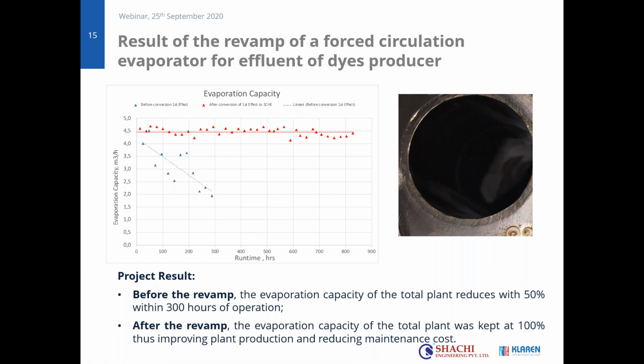So what is of course important then is what was the performance after this revamp, and you can see this in this figure, where we show the evaporation capacity on the y-axis versus time, and it's shown for the first 900 hours. We now have experience also for a longer period, and what you see is that normally, in the blue triangles, within 300 hours the evaporation capacity went from 4 cube per hour to below 2 cube per hour, which was initially what I was talking about, how fouling affects the performance. After the conversion, and you see that in the red triangles, the evaporation capacity remained constant.